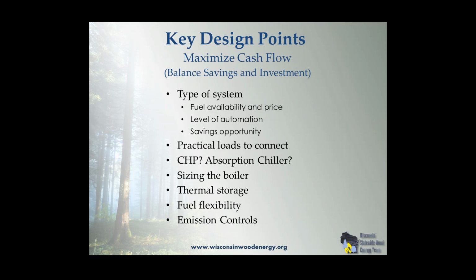Another consideration is, can you add CHP or an absorption chiller to make this system work? I'll give you a quick example of a project where the absorption chiller made a ton of sense, because what it let us do was run the boiler system to pick up an existing heat load. This was a VA hospital. They had a summertime heat load. We installed a 600 horsepower boiler that picked up about 90% of the load in the winter months. But they had about 15 to 20% of the winter load, or the size of the boiler, in the summertime, and for 5 months there was a lot of fossil fuel usage that you couldn't pick up if you would not have found an additional load.